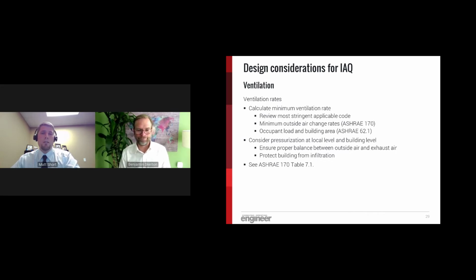Once the required ventilation is determined, perform an air balance analysis with outside air versus exhaust air to ensure that the space, level, and total building are properly pressurized. Ensure a positively pressurized building to protect against infiltration. It should be noted that you should be cautious not to overpressurize the space, which can cause side effects such as door closers not operating properly.